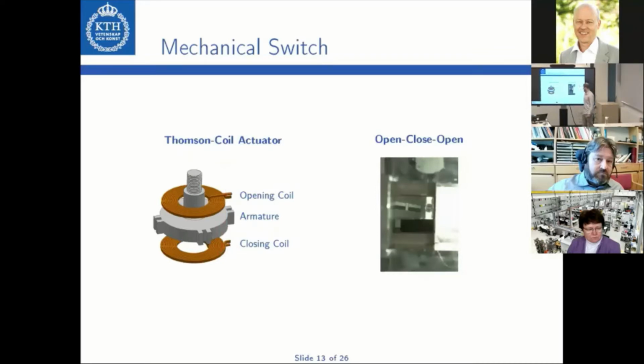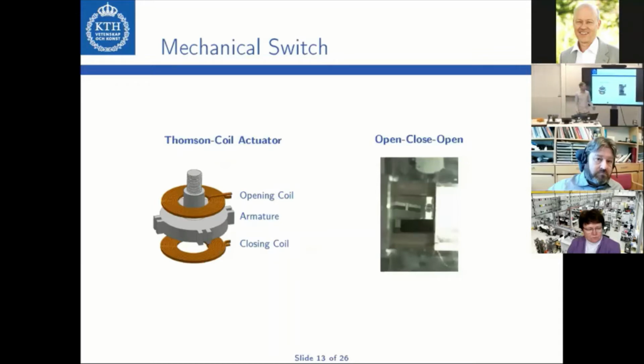We have tested this in the lab, and here I have a recording from the high-speed camera. In this case, this is the open, close, open operation of the actuator as needed for auto reclosing operation. As you can see, the armature moves down. Then after some time, the armature moves up again for reclosing. It immediately reopens again to finish this open, close, open sequence, and it worked without any problems. However, I have to mention that a substantial amount of energy is needed to make this Thomson coil actuator work.